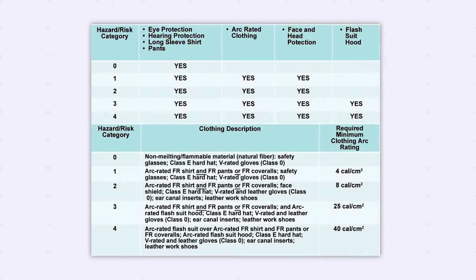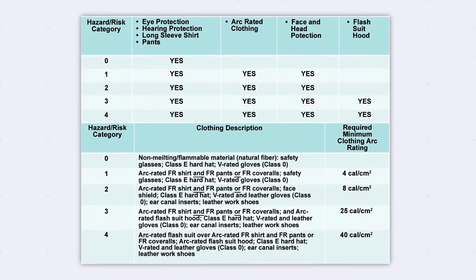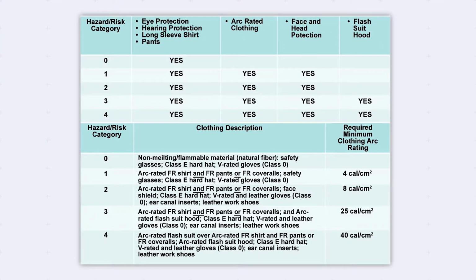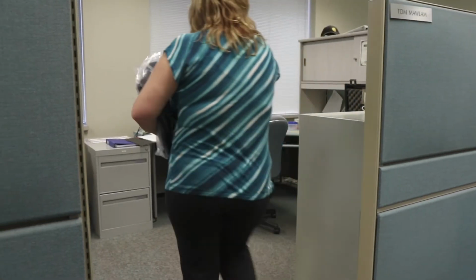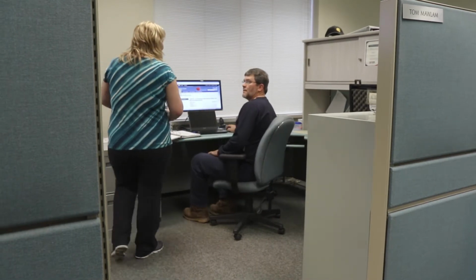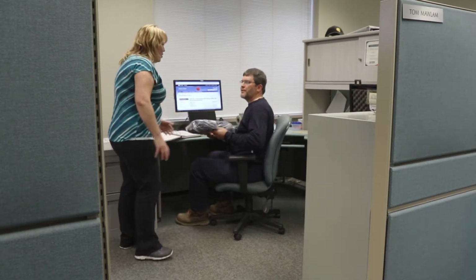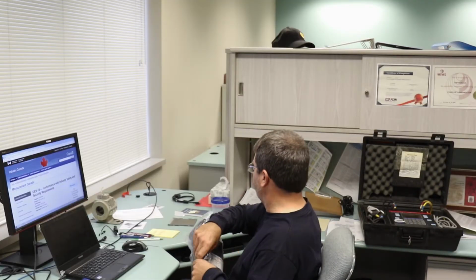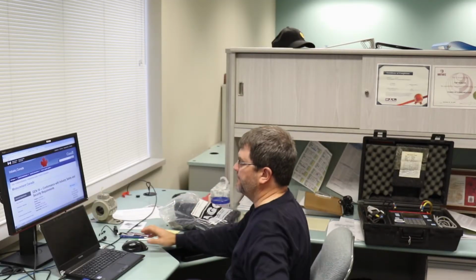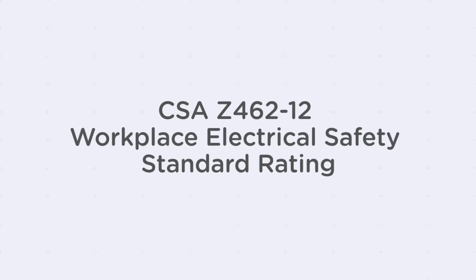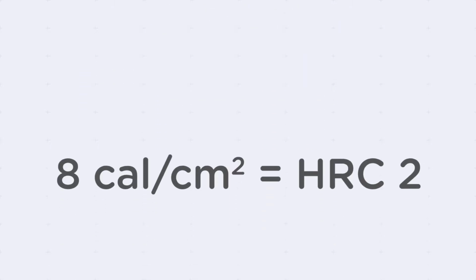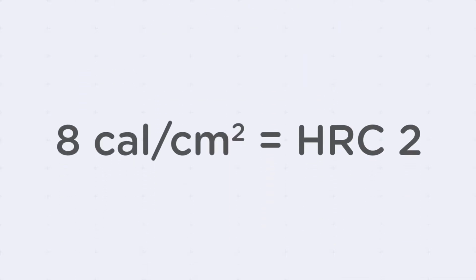The following table illustrates which articles of safety clothing are required for each hazard or risk category, as well as the arc flash rating when wearing each piece of clothing or when combining pieces of clothing. Hazard Risk Category or HRC 2 rated clothing shall be provided to all electricity inspectors who are required to wear arc flash protective clothing in compliance with the voluntary CSA Z462-12 Workplace Electrical Safety Standard rating for the applicable work, which is typically 8 calories per squared centimeter.